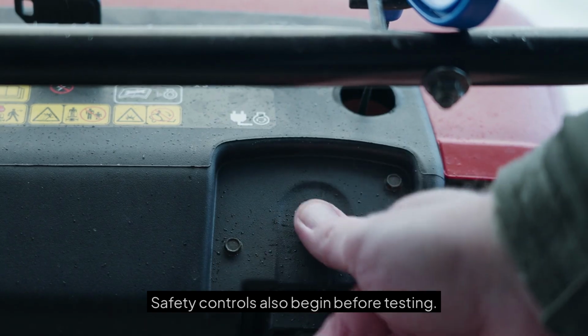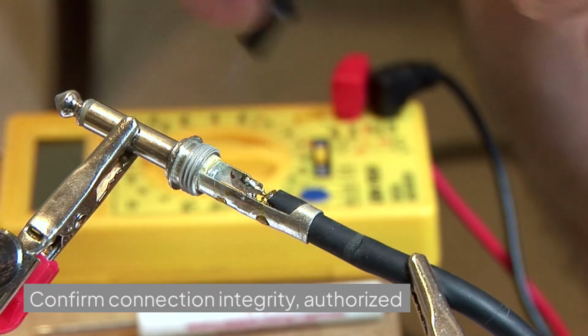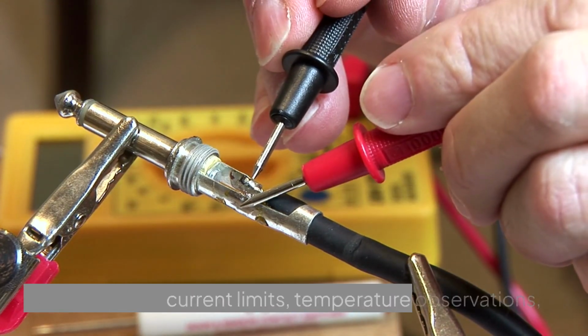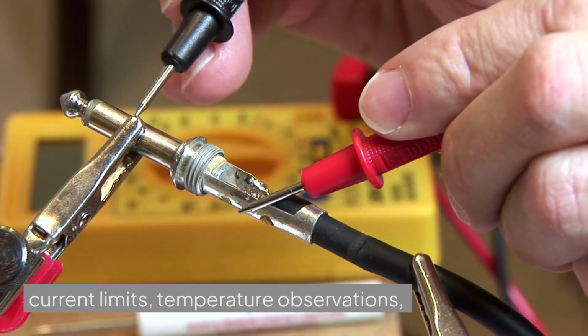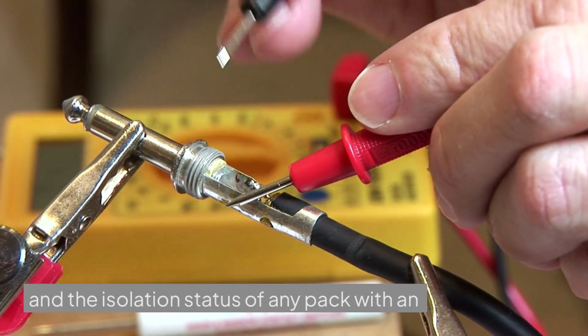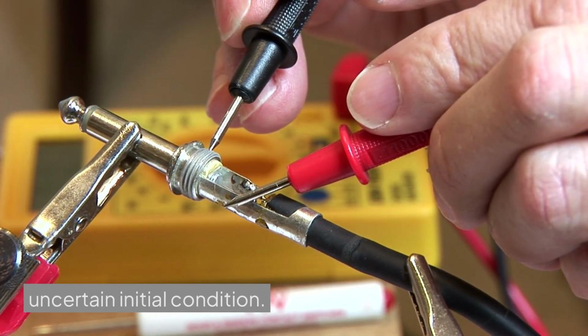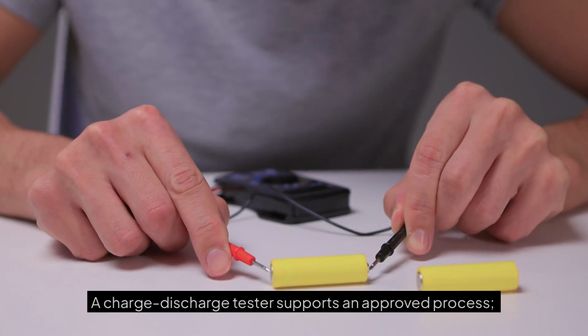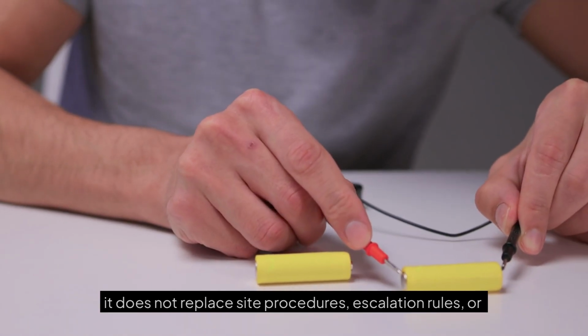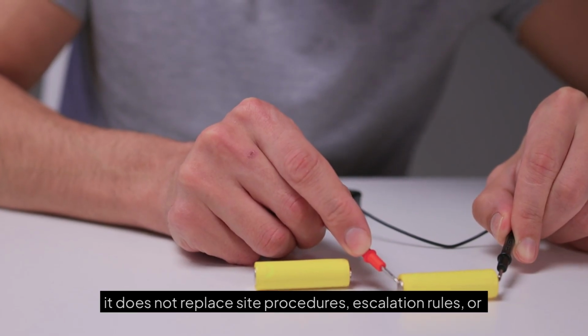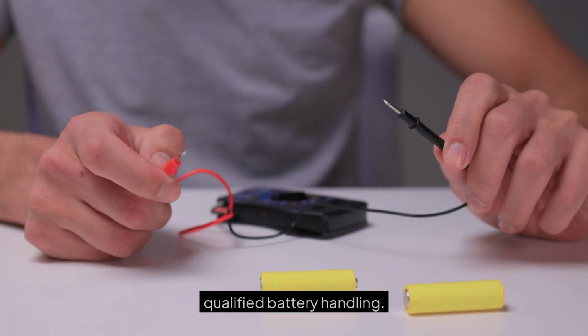Safety controls also begin before testing. Confirm connection integrity, authorized current limits, temperature observations, and the isolation status of any pack with an uncertain initial condition. A charge-discharge tester supports an approved process. It does not replace site procedures, escalation rules, or qualified battery handling.